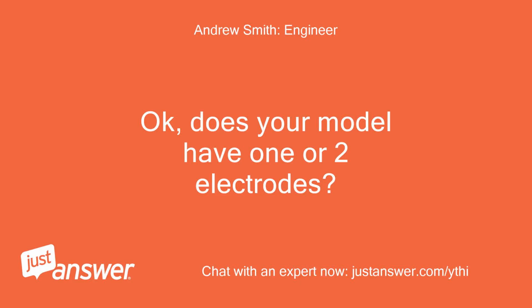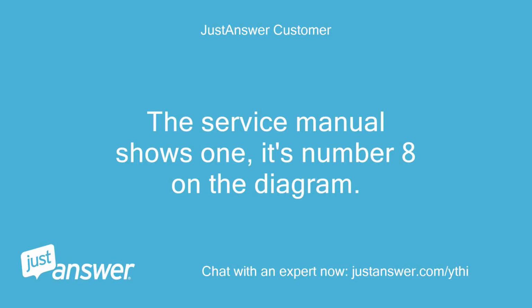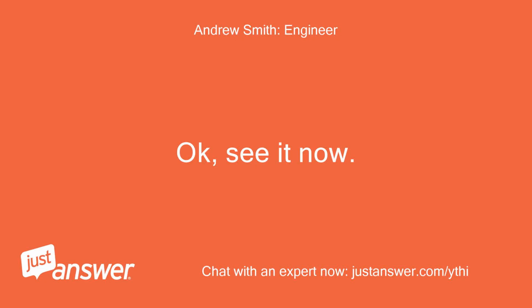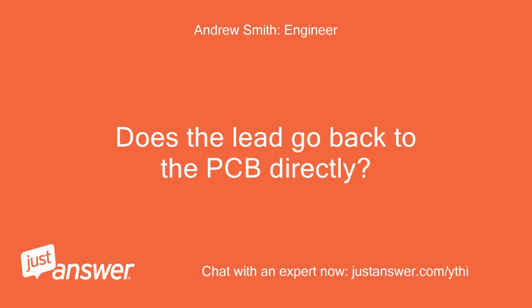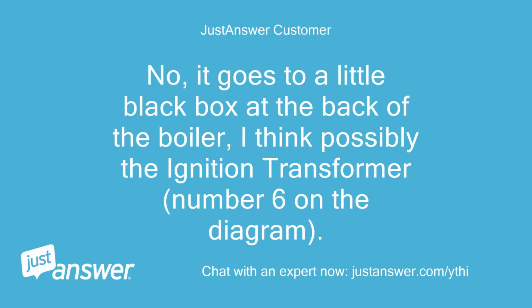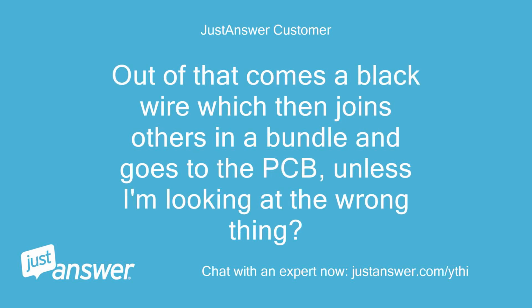Okay, does your model have one or two electrodes? The service manual shows one, it's number 8 on the diagram. Okay, see it now. Does the lead go back to the PCB directly? No, it goes to a little black box at the back of the boiler, I think possibly the ignition transformer, number 6 on the diagram. Out of that comes a black wire which then joins others in a bundle and goes to the PCB, unless I'm looking at the wrong thing?